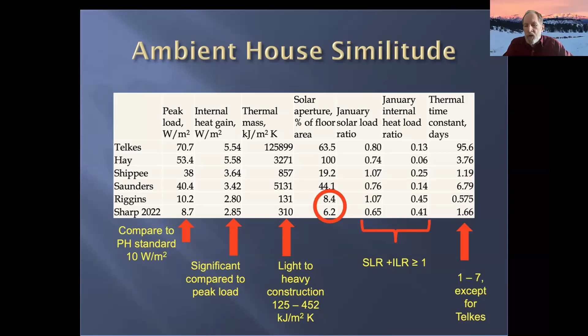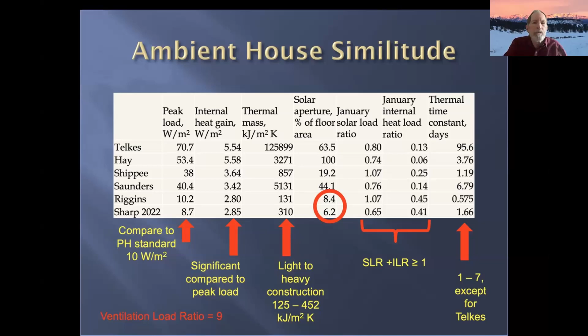And then here's where we can use those similitude parameters. If we add the solar load ratio and the internal heat to load ratio, those are our two heating sources. That needs to be in the range of 1 or a little bit more. And you can see for all of these houses, even though the designs are very different, they are all within that range. And then finally, the thermal time constant is 1 to 7, except for the Telkes building, which used phase change storage. It's much higher. A larger time constant is useful in every climate, but it definitely needs to be higher in the more cloudy climates like the Saunders house in Massachusetts. And the ventilation load ratio, as I mentioned, 9 worked for all of these houses, and you may need something larger for hotter climates, which we'll talk about a little bit later.